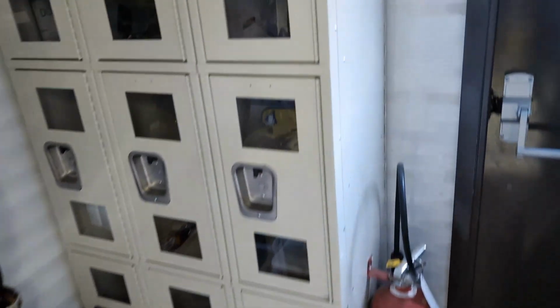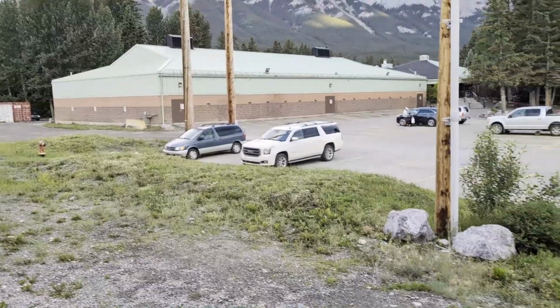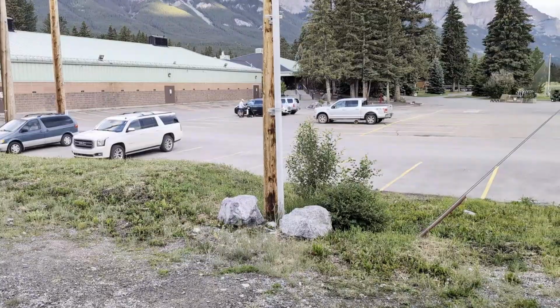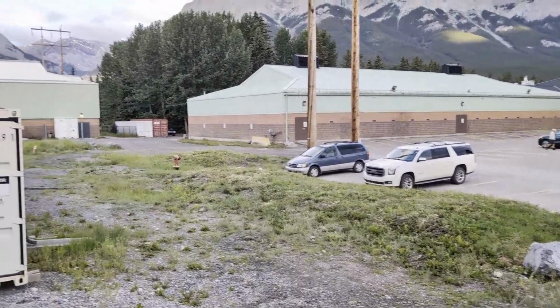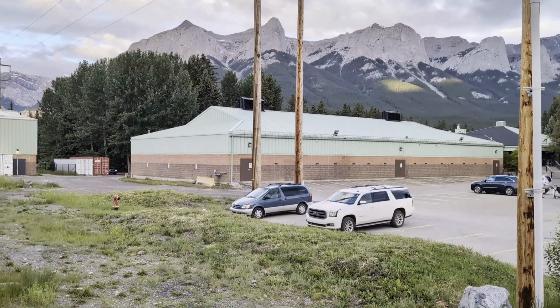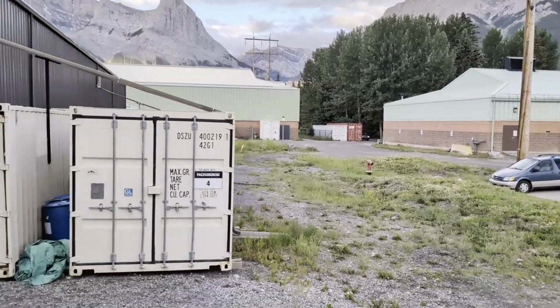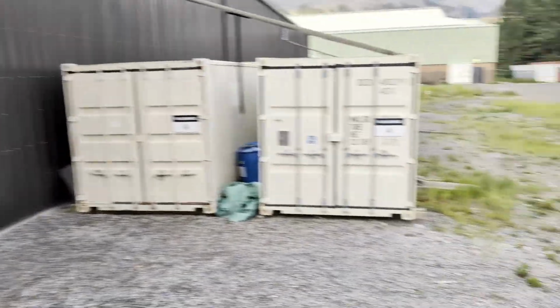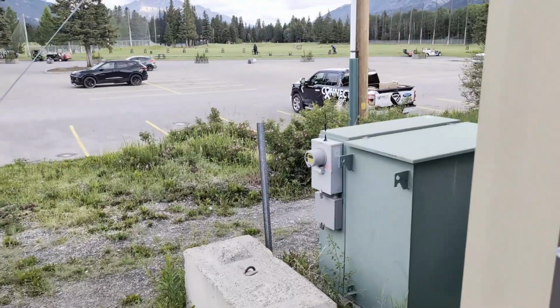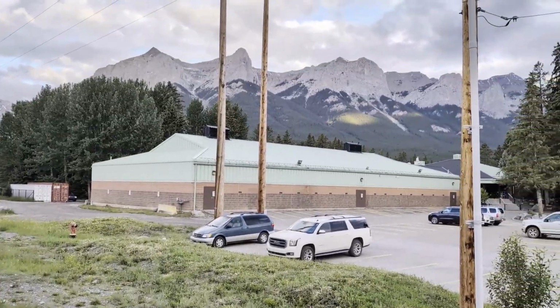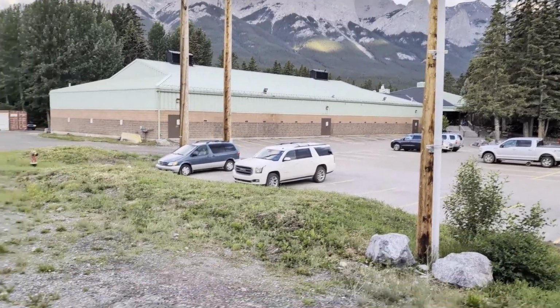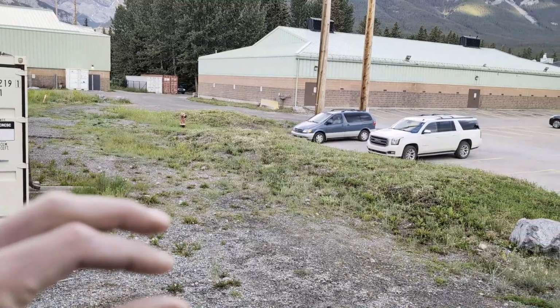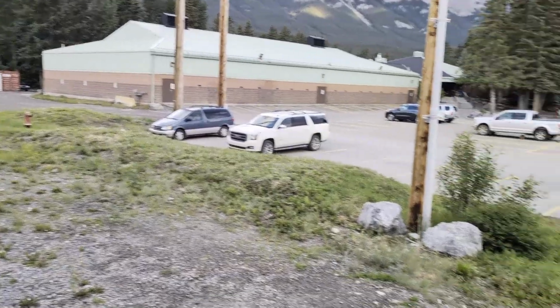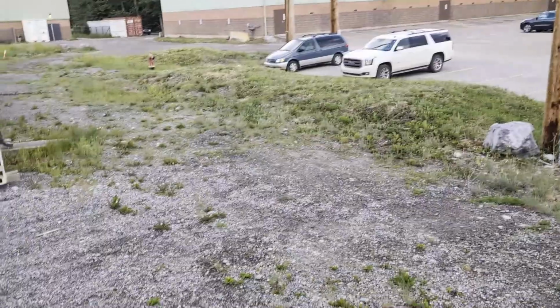And that's pretty much the process. As you can see, the curling rink makes for a great way to warm the brine up from below. You've got that floor full of brine, and the building's full of warm air, so we're basically just using that as a big heat exchanger to circulate the brine in our floor underneath the ice, and that's going to warm the ice up from below rather than heating it up from above with the air. That means, you know, it's not that thick, but you've got the ice. You want to try and keep the paint encapsulated in the ice as much as possible, and then it'll be less messy when you take the ice out, if you're lucky. All right, that's it for now.